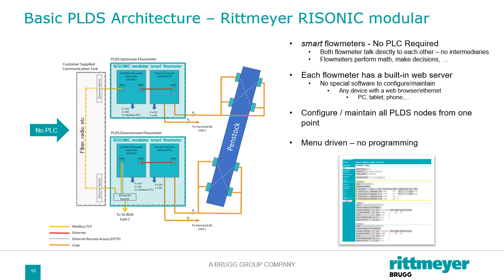If we want to do the math functions of the gross leak detection, that's a simple A minus B. We'd go into the section for defining a new function, and we would, from a pick list, select subtraction, so we can do the subtraction function. We go to the next menus to define the inputs. Again, from a pick list, we'd pick the flow from the local meter and then that remote flow that we've just set up. We hit save, and it's really that simple. It gives us a ton of flexibility, and it's so simple that we don't have to pre-program them. We can come to site and configure them right on site in a matter of hours, and no extra work in that regard.